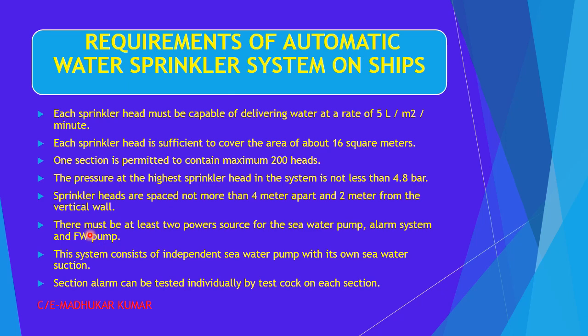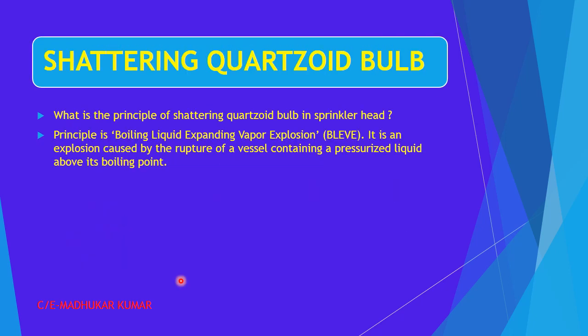Continuing with this, there must be at least two power sources for the seawater pump and alarm system and the freshwater pump. That means the main power supply and the emergency. The system consists of an independent seawater pump with its own seawater suction. A separate seawater suction is required for the seawater pump attached to it. The section alarm can be tested individually by the test cock on each section.